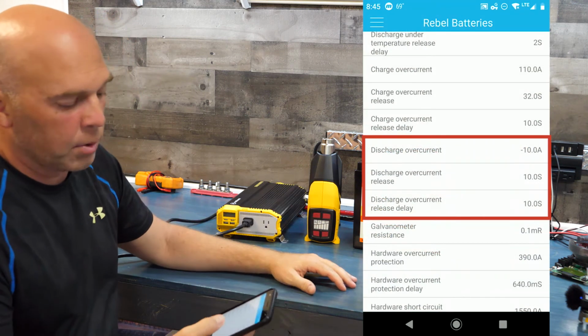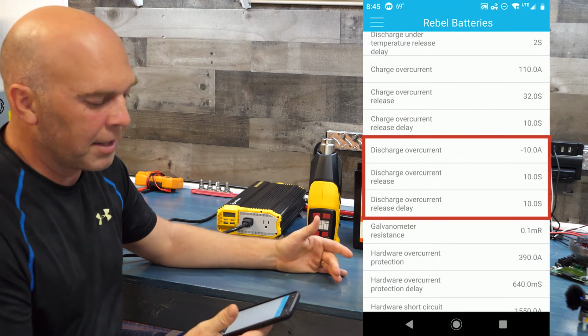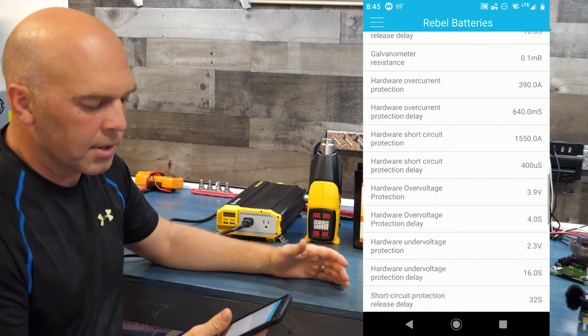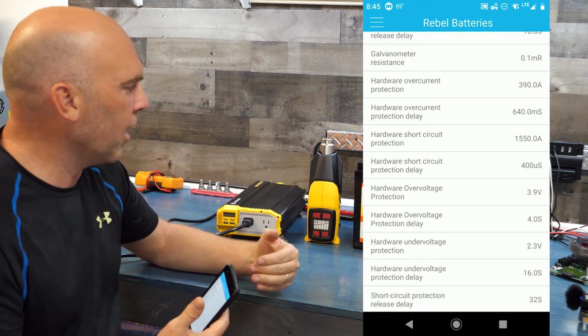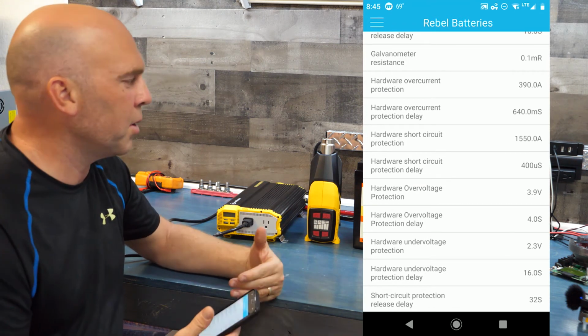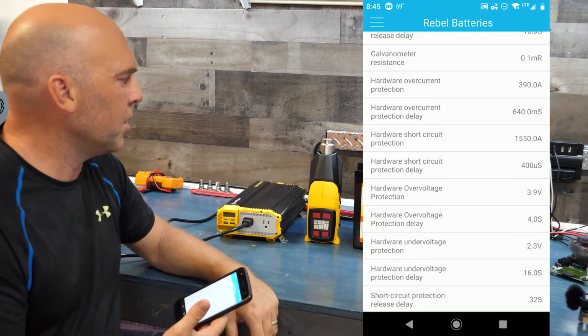So that's exactly what we just told it to do. It went over 10 amps for greater than 10 seconds, and turned itself off. That's a perfect example of how you could dial it back down. Perhaps you have a piece of equipment that you don't want to draw over 10 amps, and if it does, you want it to shut down.